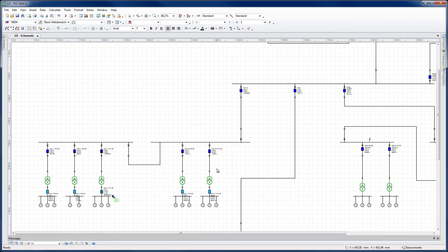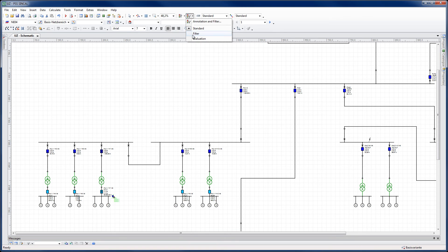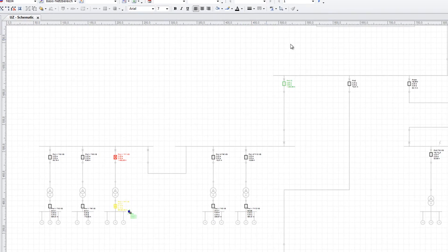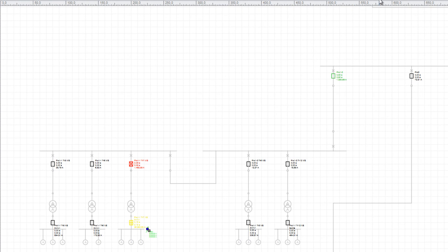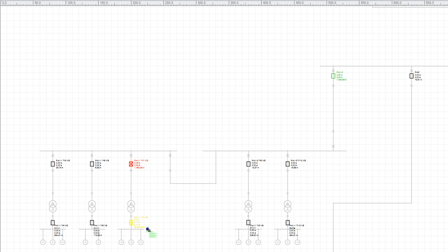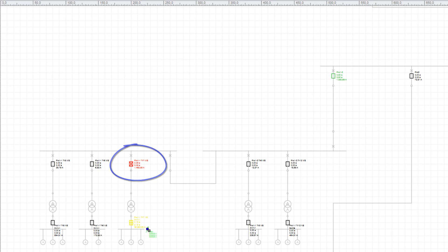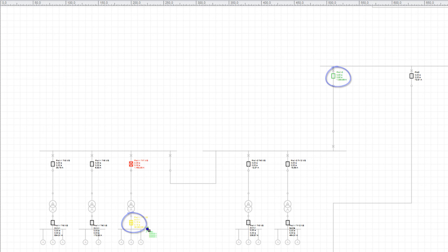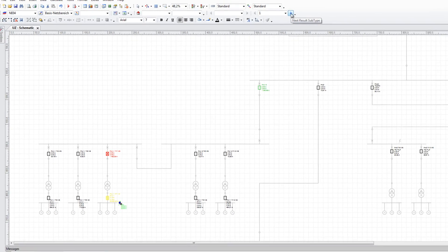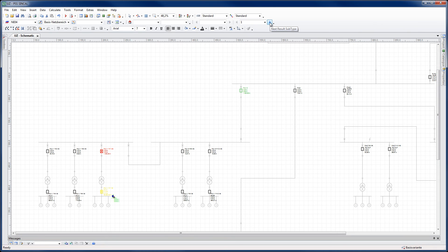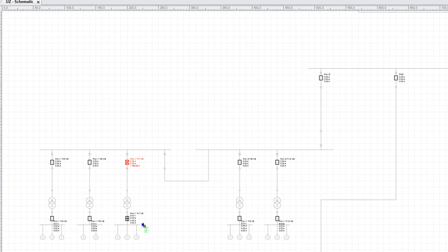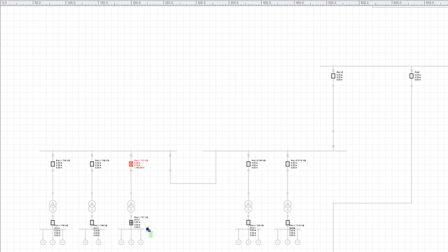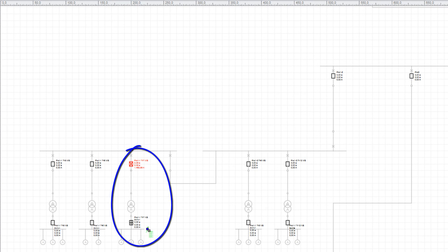Turn on filter mode. These three devices have picked up. And in the first loop, this device has tripped with a delay time of 50 milliseconds. And these two other devices are due to trip with a longer delay time. In the following loop, the fault has been cleared and the fault currents fall back to zero. As can be seen, the fault has been cleared but the devices are not selective.